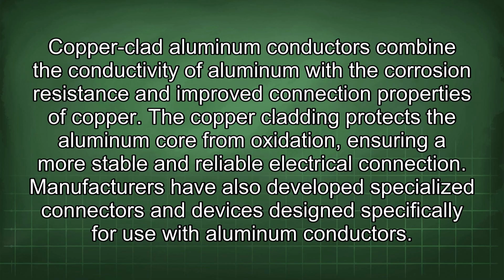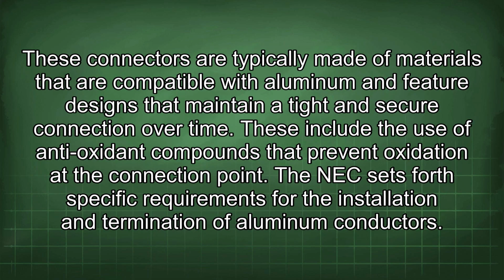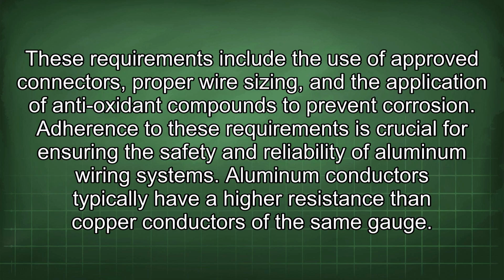Manufacturers have also developed specialized connectors and devices designed specifically for use with aluminum conductors. These connectors are typically made of materials that are compatible with aluminum and feature designs that maintain a tight and secure connection over time. These include the use of antioxidant compounds that prevent oxidation at the connection point. The NEC sets forth specific requirements for the installation and termination of aluminum conductors. These requirements include the use of approved connectors, proper wire sizing, and the application of antioxidant compounds to prevent corrosion. Adherence to these requirements is crucial for ensuring the safety and reliability of aluminum wiring systems. Aluminum conductors typically have a higher resistance than copper conductors of the same gauge.